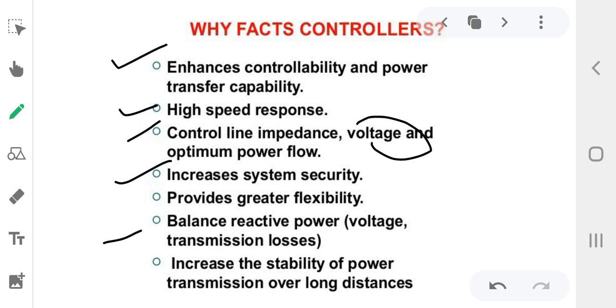Active power is the power which is used by the load connected to the receiving end, which is considered as true power or real power. But the power which is not used and only flows back and forth to support the system is called reactive power. So reactive power is nothing but the energy which is stored in the transmission line, in inductors and capacitors. ट्रान्समिशन लाईनचे जे इंडक्टर्स आणि कपॅसिटन्स हे कंपोनंट्स आहेत, त्यामध्ये एनर्जी जी काही स्टोअर होते, that stored energy will be considered as a reactive power. And to control that reactive power, to increase the transmission efficiency, we use the FACTS controller in the transmission system.